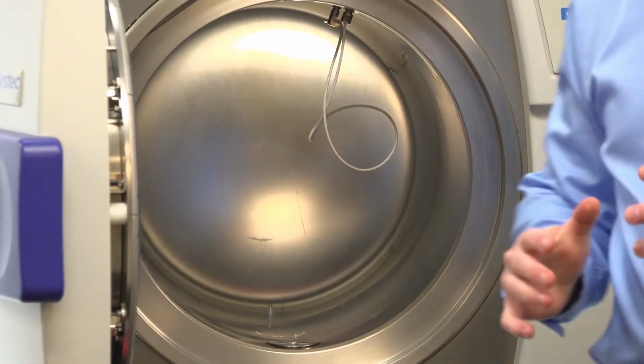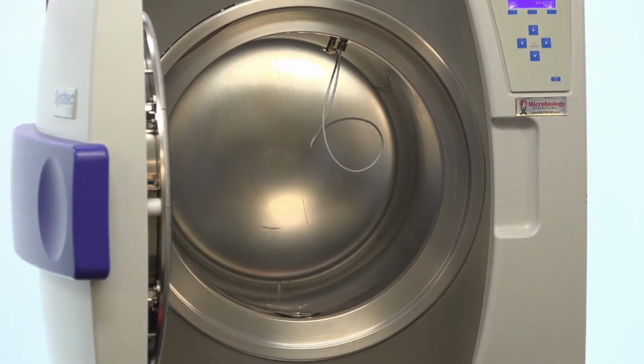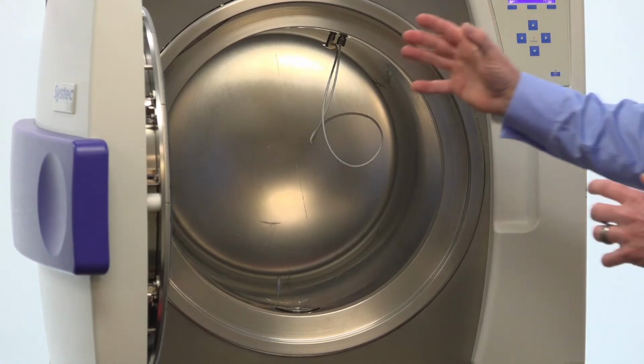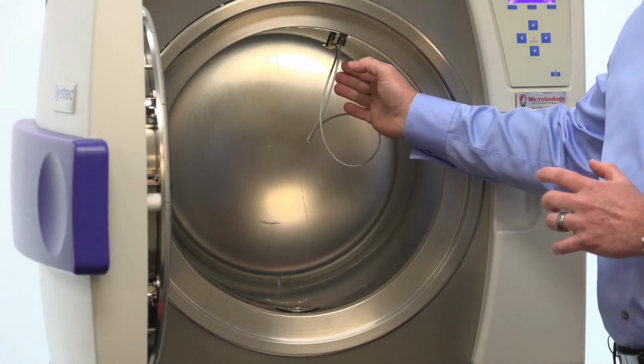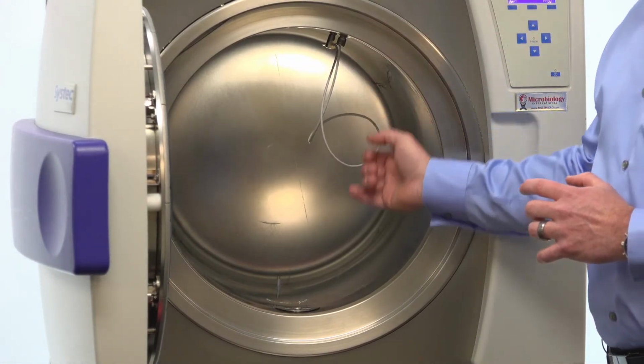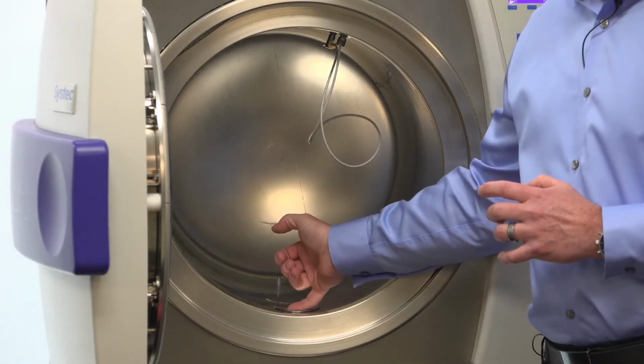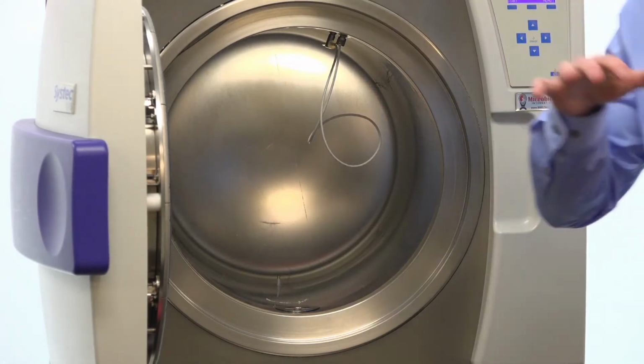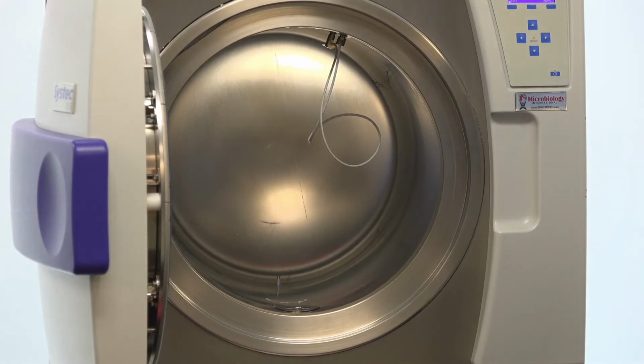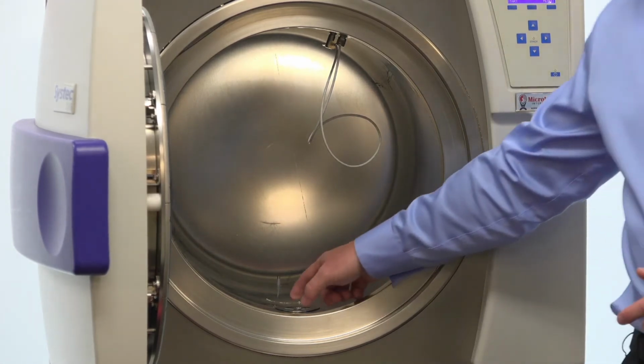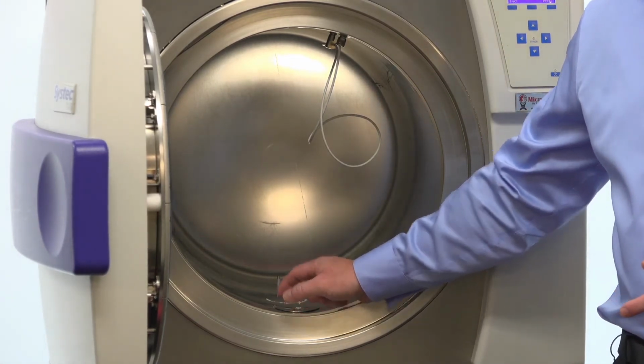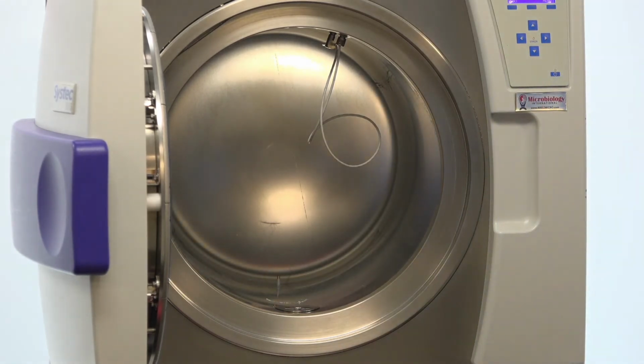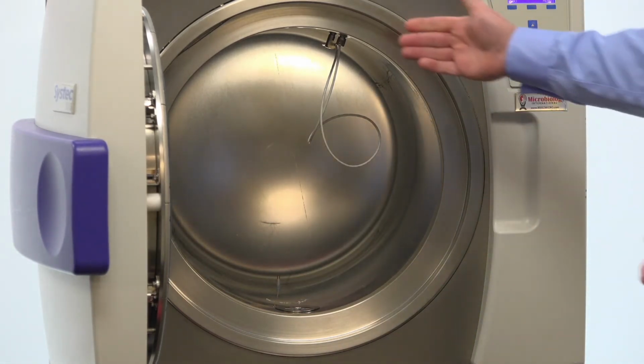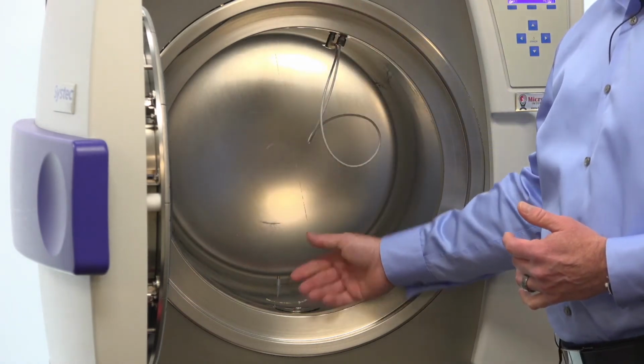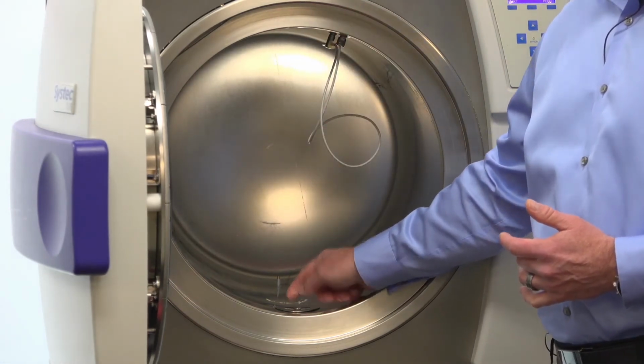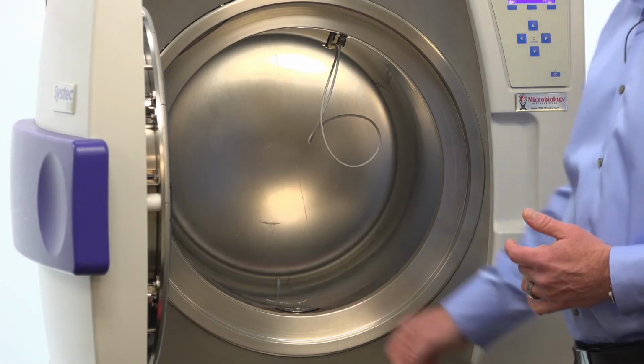So when we're actually running a cycle, whether it's instruments or waste, remember we had said that for liquid cycles, we're going to use our flexible PT100 probe. There is also a PT100 probe directly in this drain line, which is the area where the air will be evacuated from the instrument. So we will be measuring pressure and temperature at this drain line for all instruments and waste cycles. That way we know the rest of the autoclave is completely full of steam. Because once we achieve that here, then we know we don't have any air pockets inside of the unit.